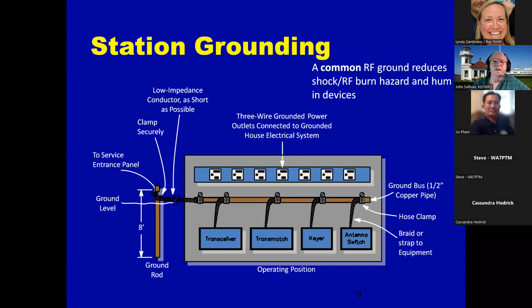But if you can't get an 8-foot rod in, you might want to use multiple shorter ones. They just need to all be bonded together. That's another principle: we want everything at a common ground. All of your ground wires of any kind should be connected, bonded together, so there's a common ground. Use copper, short and straight connections to everything. That's an example of setting up a grounding system for a station, and we're going to talk a lot about grounding today.